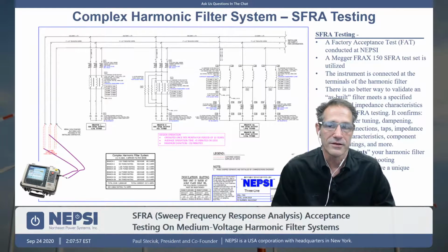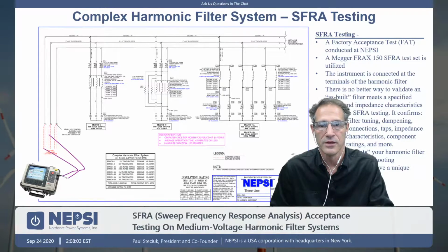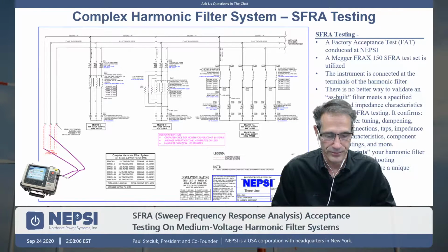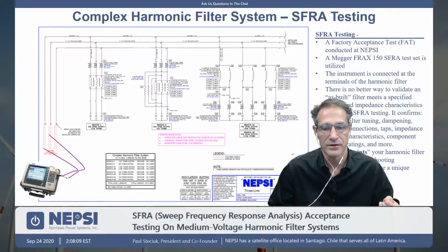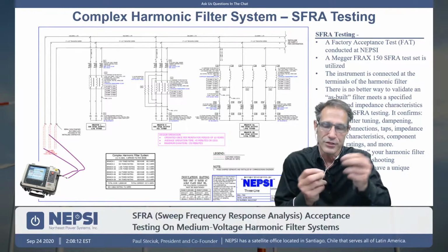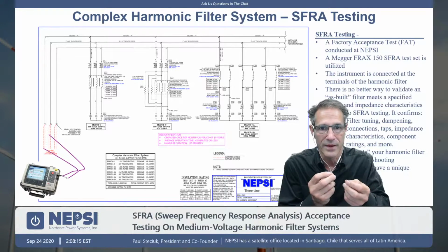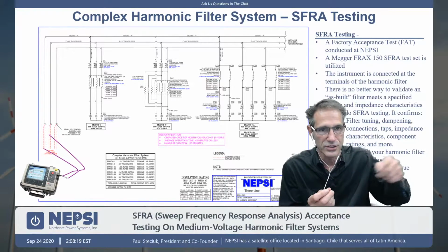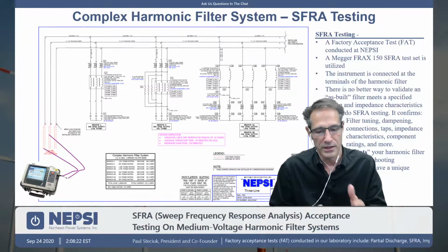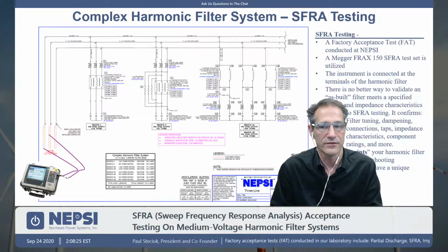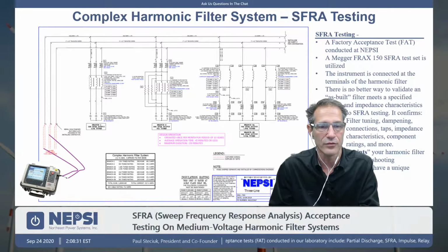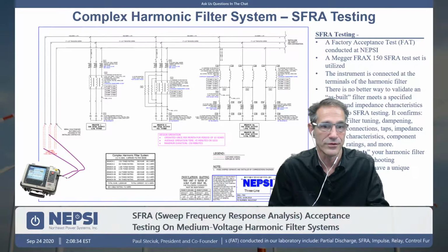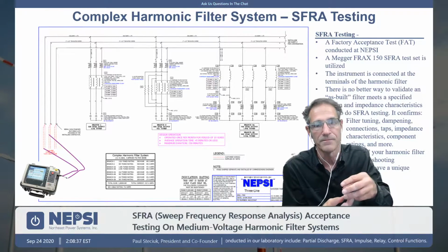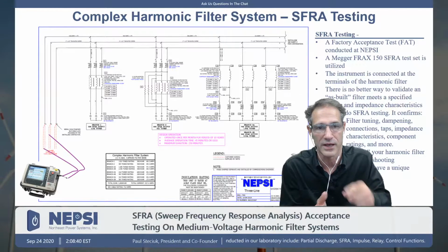The SFRA test set is commonly used in testing transformers, transformer windings, and major power transformers. So it's used in the power substation to check the health of a power transformer. If there is any kind of shift in the winding of a power transformer, its capacitance and impedance characteristics change, and you'll get changes in the shape of the curve. So in a substation environment, you're typically using it on the power transformer to determine the health of the transformer. Has any change occurred from the date it was manufactured to some time in the future? Say you had a fault on that transformer and the winding shifted a little bit. Well, its capacitive characteristics would change and you would get a shift in that impedance profile.